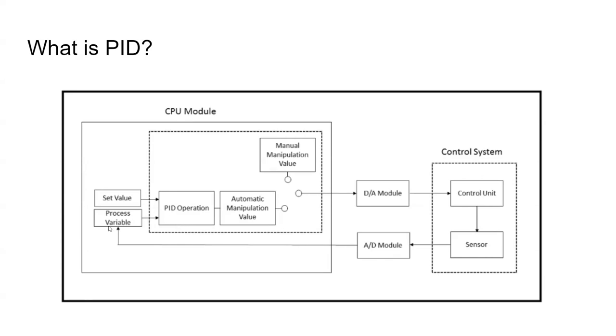The manipulation value is the response the PLC gives to an analog card, digital card, or a VFD. Some type of operation is generated based on the inputs — the set value and process value — because we need to know when to turn on air conditioning or a furnace. You can do a manual manipulation value, but I don't recommend it. That is like turning cruise control off and putting your foot on the accelerator — it's not going to help you save gas. In the long run, a PID application will always surpass manual control.